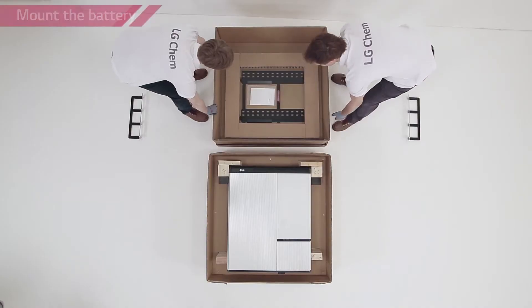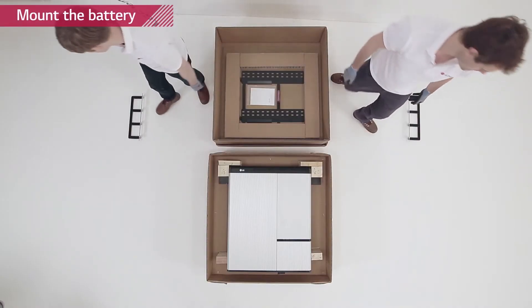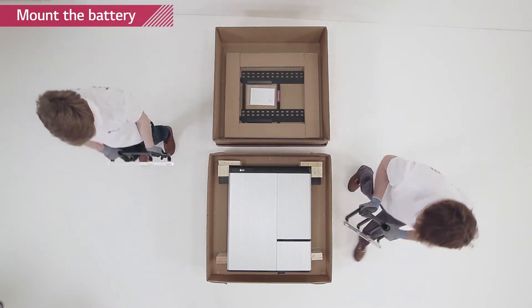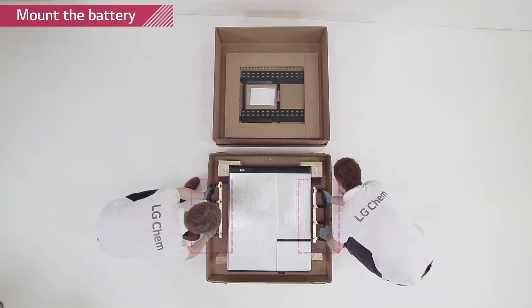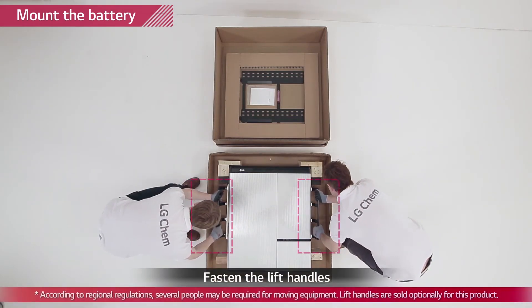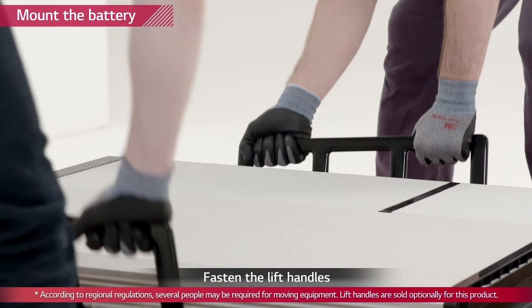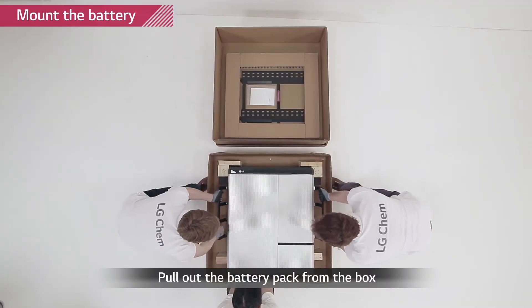Attach the lifting handles to the hex socket screws located at the back of both sides of the RESU pack. Lift the battery pack using the handles. Handle the RESU10H carefully as it weighs about 100 kg. Note that the wall on which the battery pack will be mounted must have the capability to support weight over 150 kg.